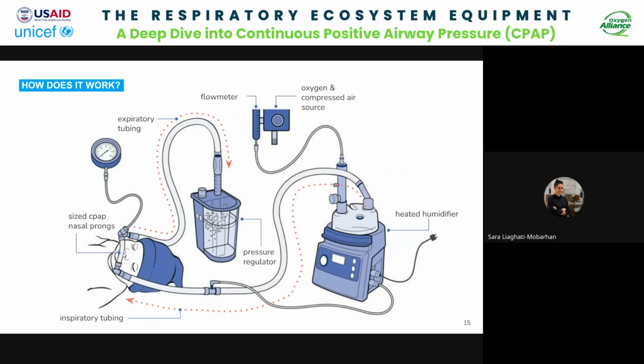To think about the way that the CPAP works, you can have another analogy. So imagine a straw placed in a glass of water. So when you blow air through the straw, you create bubbles. And in a similar way, bubble CPAP blows air through a tube that's partially submerged in a container of water. And the depth of this tube in the water creates a certain amount of pressure, just as it does when you're blowing into a glass with a straw. And this air, along with the pressure that's created by the bubbles, is delivered to the baby's lungs through special prongs. And this constant pressure, as Leah was saying, there's different types of pressure, but this constant pressure from the bubble CPAP helps to keep the baby's airways open, which makes it easier for them to breathe.